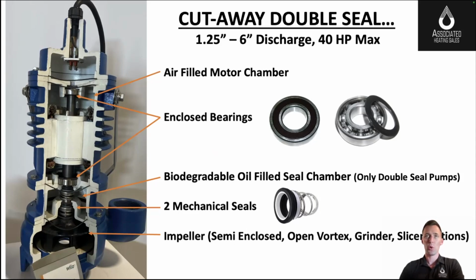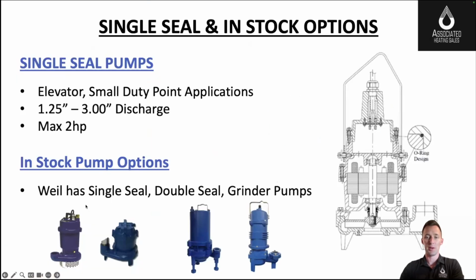So at about 2 horsepower or greater, you have double seal pump options. It makes sense. You're paying a larger upfront cost. You want this pump to last longer, you get the double seal pump, but the lower price point becomes the single seal pumps, which you see here. We have one mechanical seal and we've lost that seal chamber. So these typically head into elevator pump systems or small duty point applications that don't run very often. 2 horsepower or less, 1.25 all the way up to about 3 inch on the single seal options.